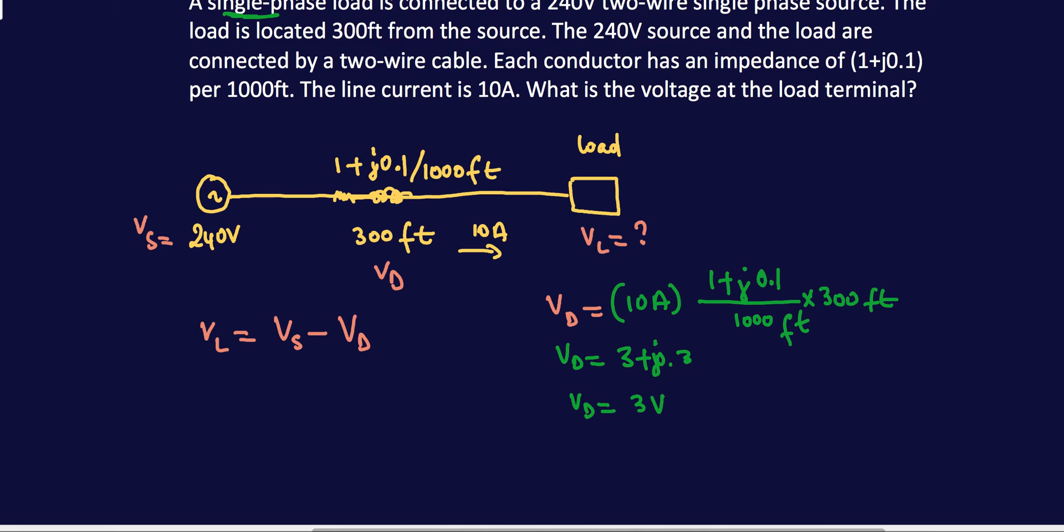So you have a neutral—the neutral return current will be equal to the phase current. Your voltage drop is really not 3V; it's actually times two because you have to take into account the return path. So remember that: single phase, take into account the return path.